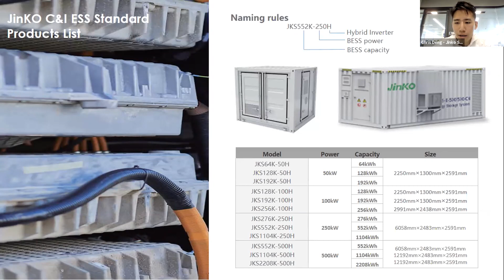Based on the naming rules, we can tell exactly how the system is configured. The 250 is the PCS power rating. Then there's how much energy can be stored, the 552K, which is the battery capacity. And H stands for hybrid inverter, meaning it can connect with the PV side and also do power conversion between the battery and the PCS.